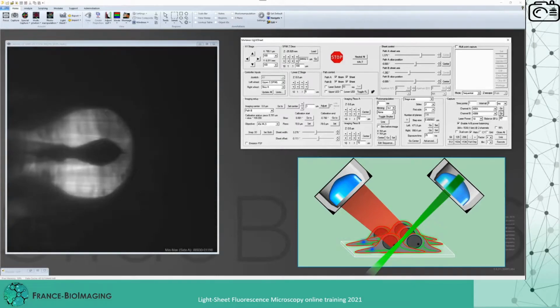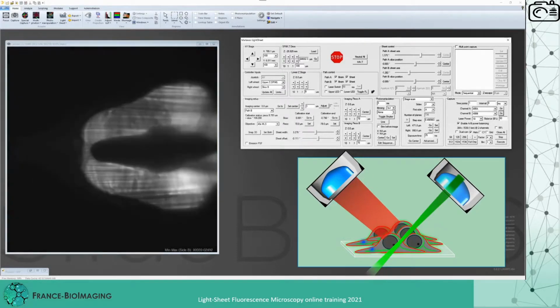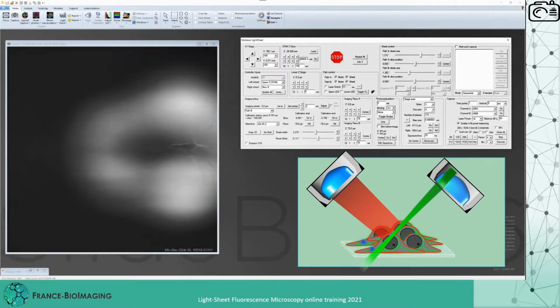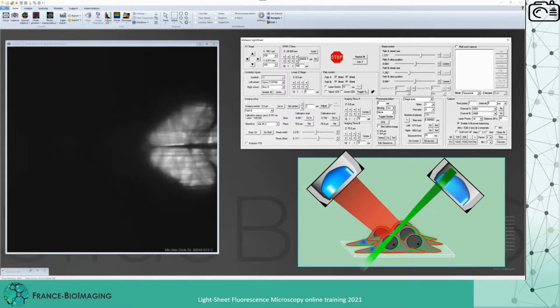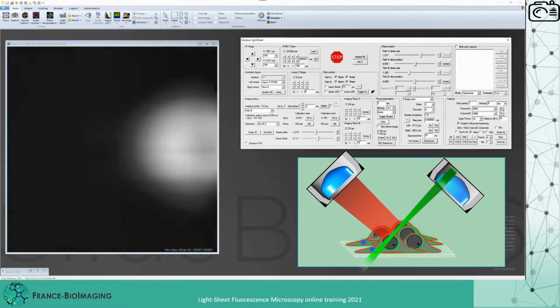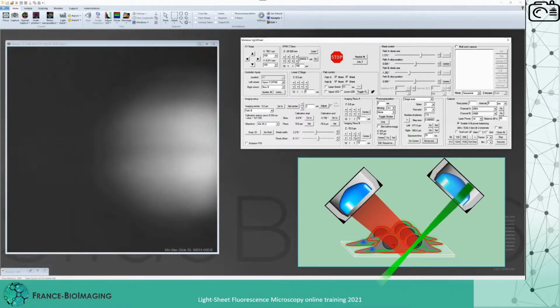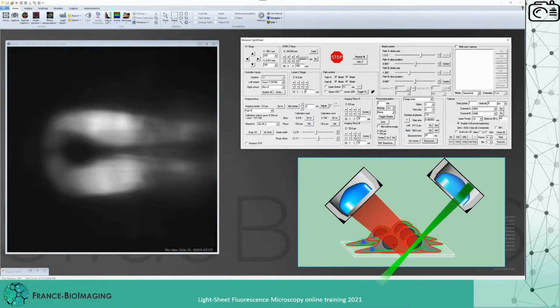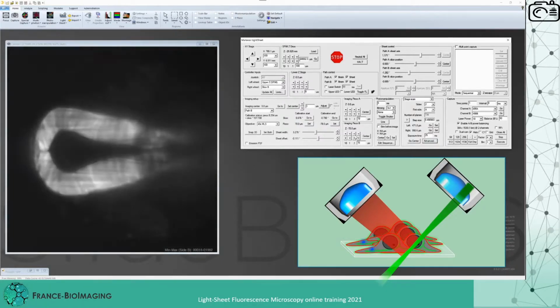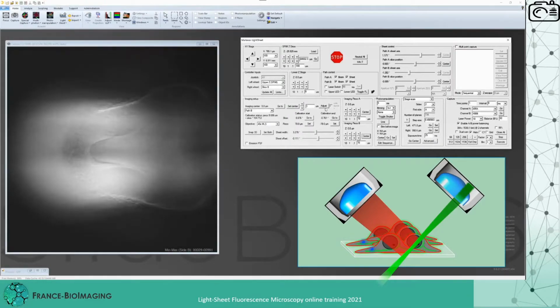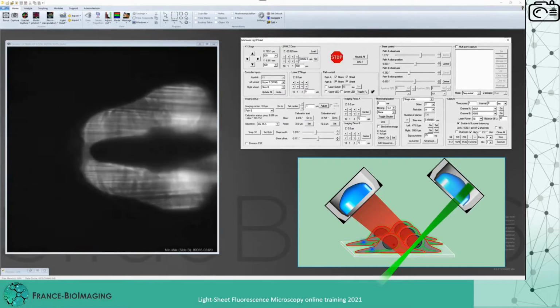The procedure is identical for path B. Again, we are shifting the objective to an extreme position and matching the light sheet position. So that's plus 70, that would arrive around here. So we set that, then shift to minus 70 and again find the right position, which should be around here. Once this is done, we center both objectives and click Adjust to check that all is good. The calibration is now complete and we are now ready to proceed to acquiring our sample.